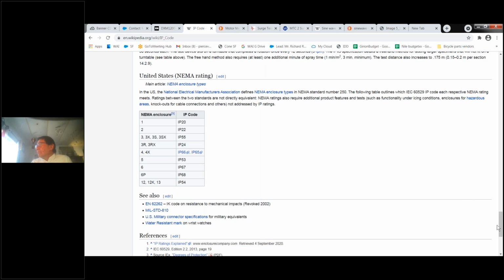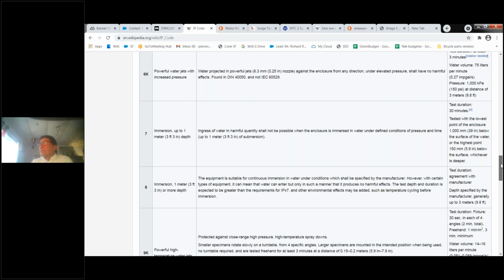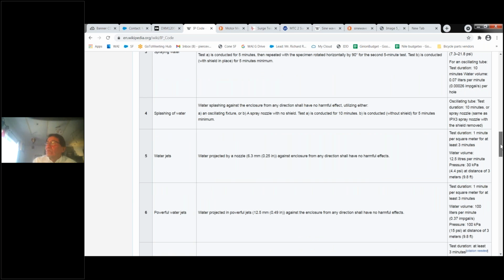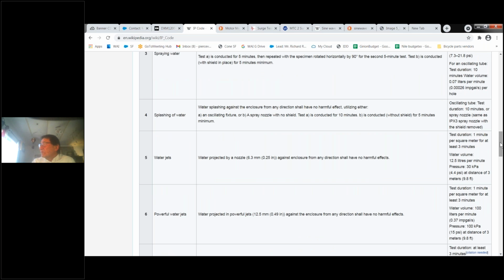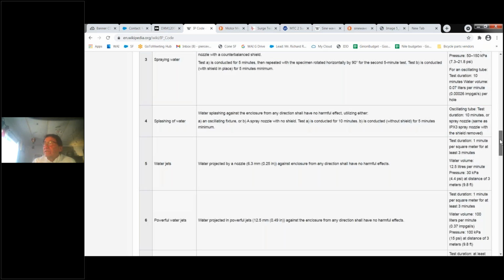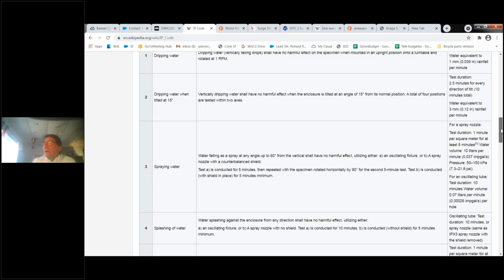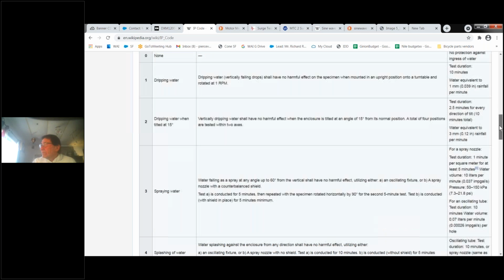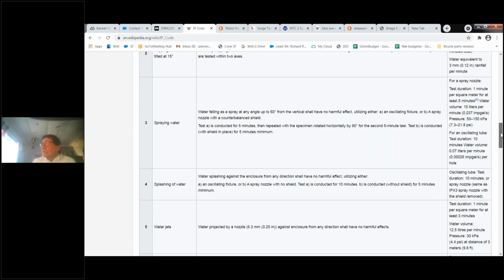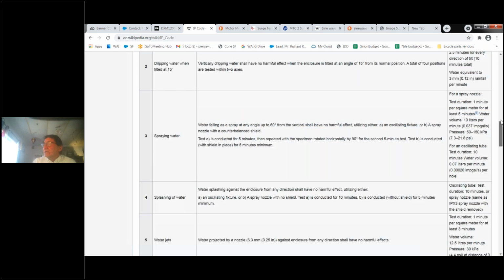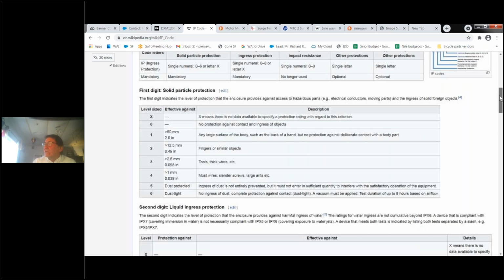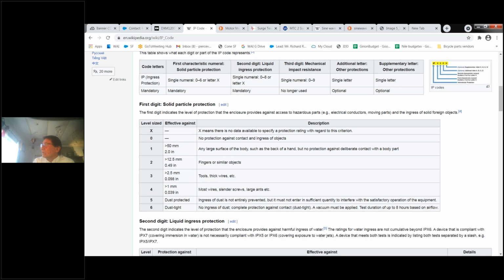So if we go back up to our charts, 5, 4, let's take the second digit first. 4 is we're good for splashing water, which means we're good for spraying water, which means we're good for dripping water or rain tilted at 15 degrees. And that's the second digit. The first digit in IP54 is a 5, which is dust protected, ingress of dust not entirely prevented, but must not enter in sufficient quantity to interfere with satisfactory operation of the equipment.